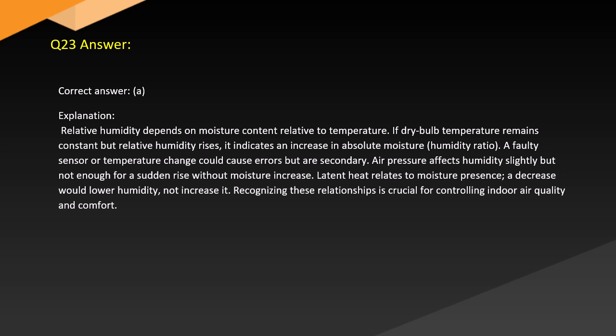Answer. Correct answer: A. Explanation. Relative humidity depends on moisture content relative to temperature. If dry bulb temperature remains constant but relative humidity rises, it indicates an increase in absolute moisture, the humidity ratio. A faulty sensor or temperature change could cause errors but are secondary. Air pressure affects humidity slightly but not enough for a sudden rise without moisture increase. Latent heat relates to moisture presence. A decrease would lower humidity, not increase it. Recognizing these relationships is crucial for controlling indoor air quality and comfort.